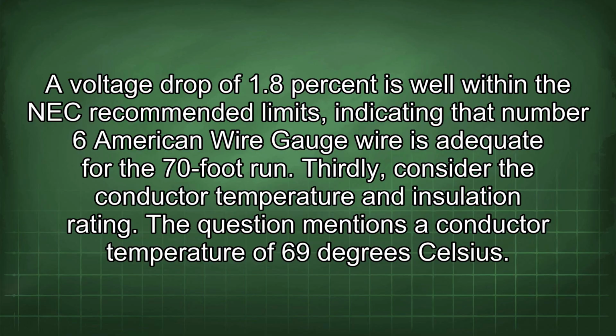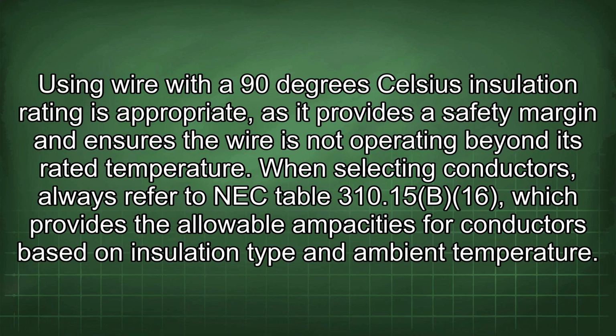Thirdly, consider the conductor temperature and insulation rating. The question mentions a conductor temperature of 69 degrees Celsius. Using wire with a 90 degrees Celsius insulation rating is appropriate, as it provides a safety margin and ensures the wire is not operating beyond its rated temperature. When selecting conductors, always refer to NEC Table 310.15(B)(16), which provides the allowable ampacities for conductors based on insulation type and ambient temperature.